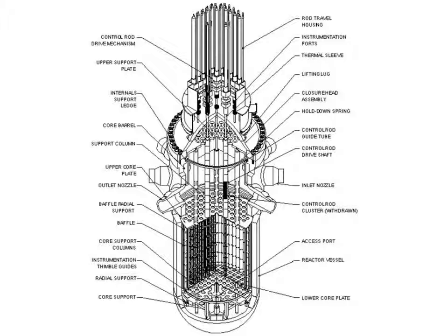In the case of an emergency, these control rods can be dropped into the reactor, even if there is no external power, because the control rods are suspended above the reactor using electromagnets. If there is a power failure, current to the magnets will cease and gravity will pull the control rods into the core. During normal reactor operation, these control rods can be manually inserted to different depths within the reactor by an operator.